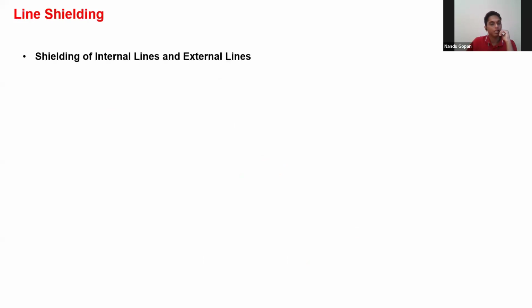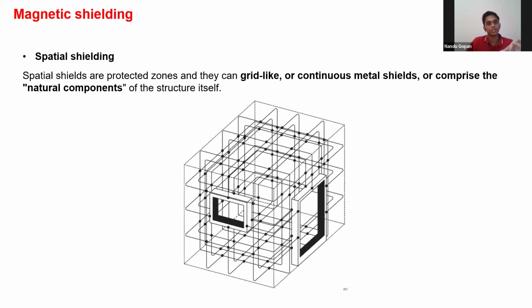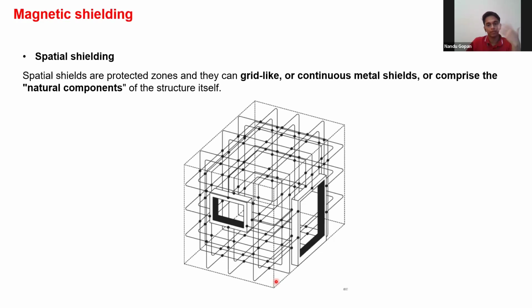Next is line shielding. For spatial shielding, you probably need around 5 meter by 5 meter grids, or if you're connecting the RCC, that's more than enough. If you want more calculation on this, Annexure A or Annexure B of the standard gives proper calculations on how to select the spatial shielding. I won't teach the calculation part much, because that would need a separate webinar - it's quite complicated.